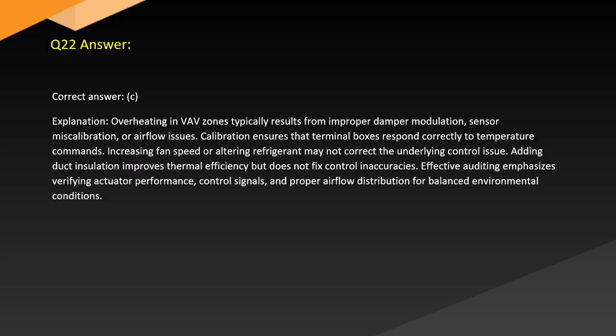Answer. Correct answer. C. Explanation. Overheating in VAV zones typically results from improper damper modulation, sensor miscalibration, or airflow issues. Calibration ensures that terminal boxes respond correctly to temperature commands. Increasing fan speed or altering refrigerant may not correct the underlying control issue. Adding duct insulation improves thermal efficiency but does not fix control inaccuracies. Effective auditing emphasizes verifying actuator performance, control signals, and proper airflow distribution for balanced environmental conditions.